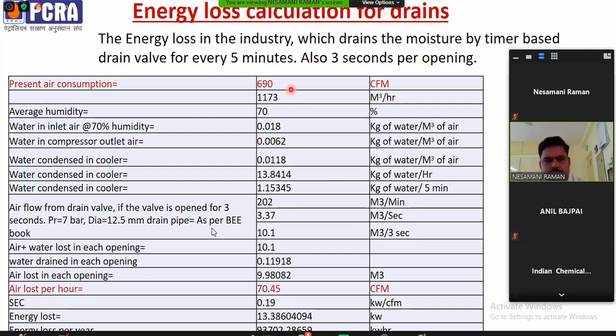So I tried to calculate the loss. Whenever it opened, it started to push out a little bit of moisture with the air, so I tried to calculate how much air loss was happening. I took a humidity of 70% in that area. For every pressure, we get a water level in the air. So I took the atmospheric water level as well as the high pressure water level. The difference is the water condensed in the cooler. There was a small hole, a 12 mm drain.